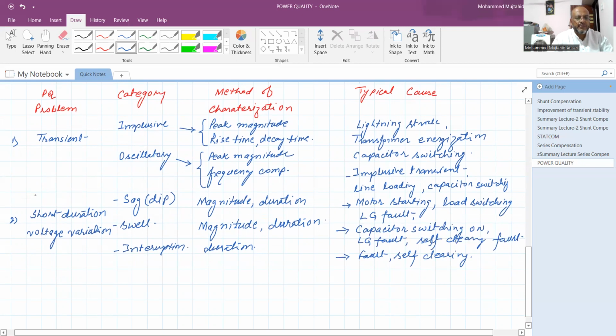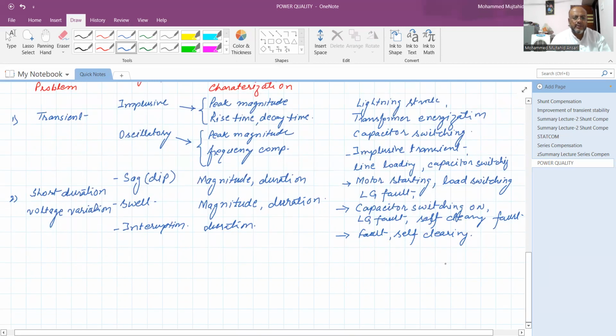So this is the first problem, a transient. It has two parts, impulsive and oscillatory. The method of characterization means it is observed by its peak magnitude, rise time and decay time. Similarly, the oscillatory transient is characterized by peak magnitude and frequency component. Short duration variations are sag, swell and interruption. Sag is measured with magnitude and duration. Similarly, swell is characterized by magnitude and duration, and interruption by duration. And these are some typical causes of short duration voltage variation.